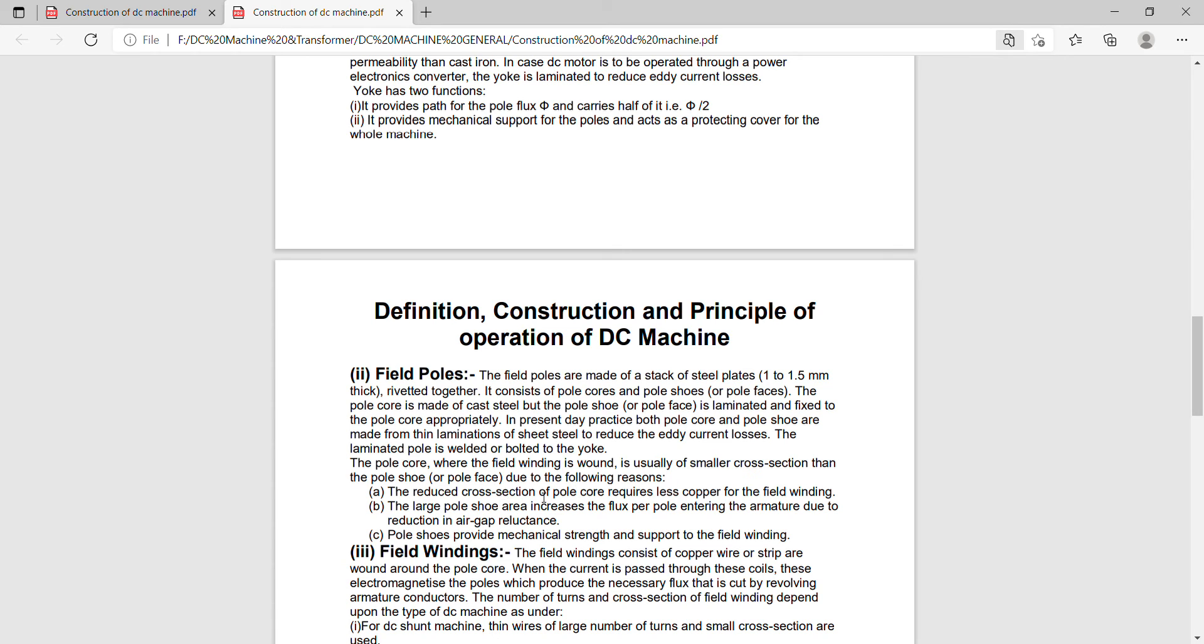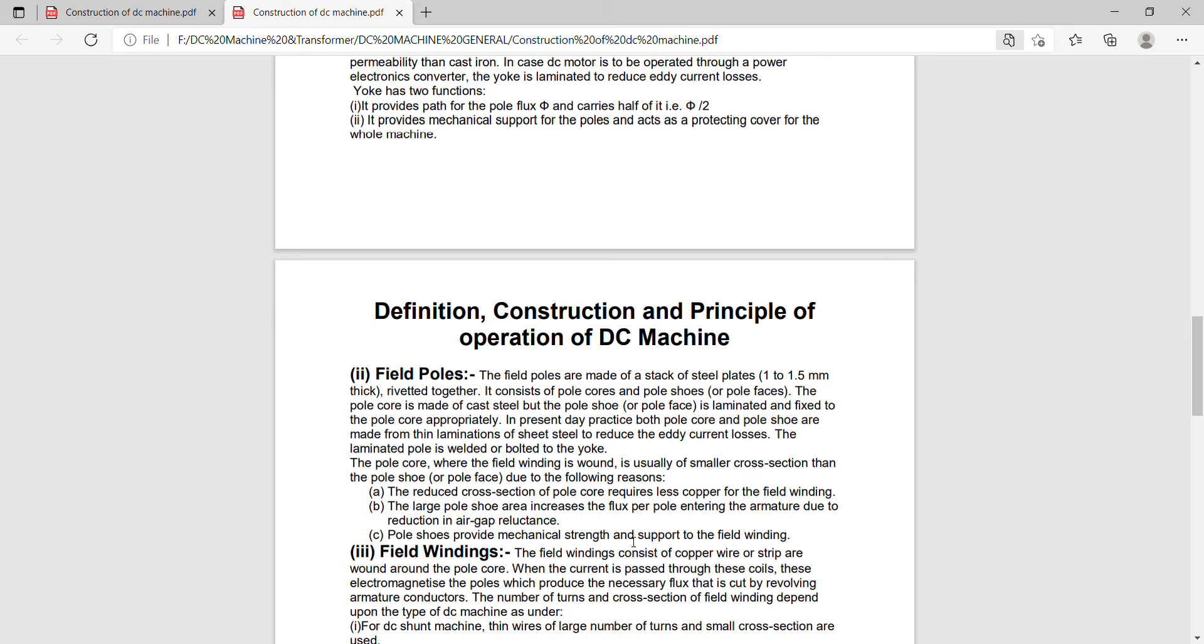Due to the following reasons: the reduced cross section of the pole core requires less copper for the field winding. Second, the large pole shoe area increases the flux entering the armature due to the reduction in the air-gap reluctance. And third, pole shoe provides mechanical strength and support to the field winding. This is the main function of the pole shoe.